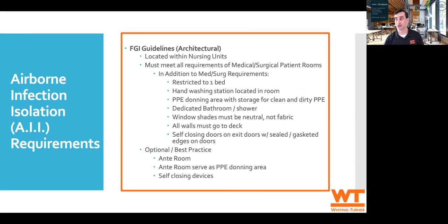Mechanically, the design of negative space is not overly challenging in itself. There does come a challenge when we analyze the upgrading of the existing infrastructure. You need to take into consideration the CFM capacity of your existing air handlers and the chilled water system. Since you're not recovering that cooling or heating because it's a once-through system, you're going to have additional cooling needed. And even the electrical equipment services need to be looked at and addressed.